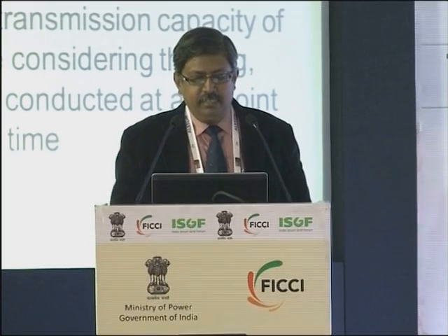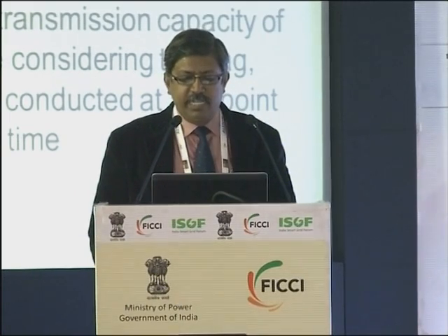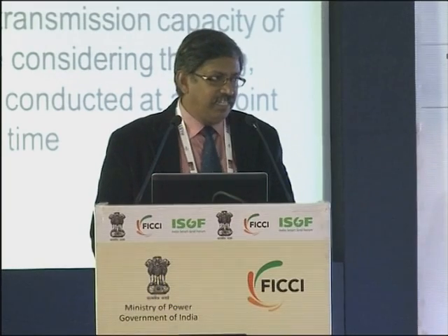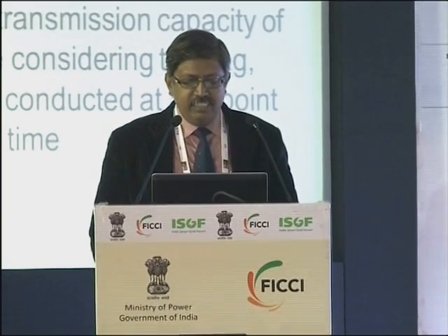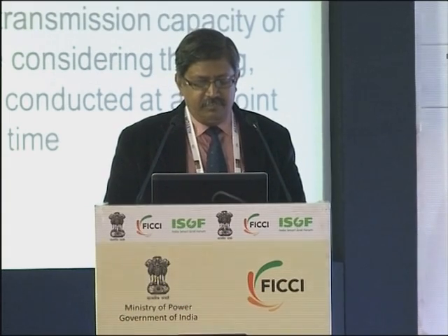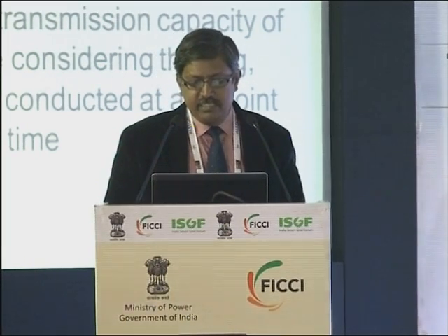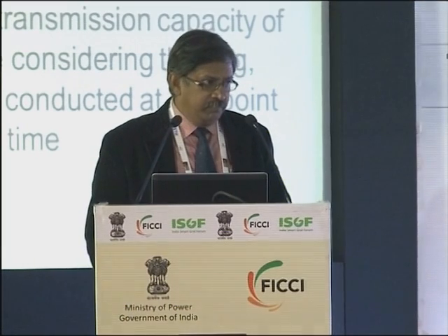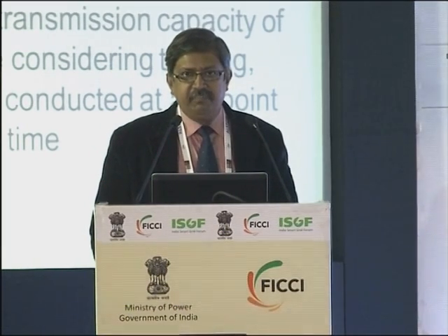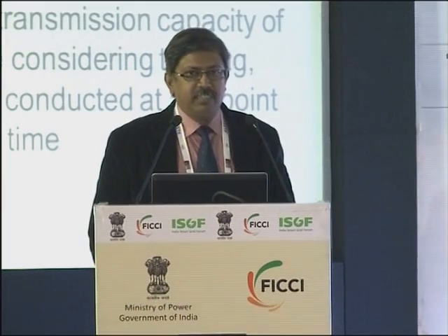So what is DLR? Simply put, it is the overload rating of transmission lines. But life is not so simple. DLR is the real-time transmission capacity of a transmission line considering the sag, weather and current conducted at any point in time. So there is a safe rating for the lines, but we can actually stretch it a little bit more by considering the real-time conditions of weather and other operating conditions. And that is what we call dynamic line rating.